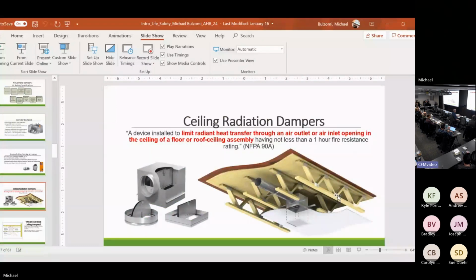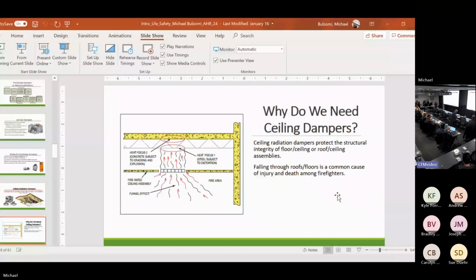Actuators, ceiling radiation damper. One job for a radiation damper: limit radiant heat transfer in a floor ceiling or roof ceiling assembly. So let's call this a membrane penetration. Right above us, I got a T-bar ceiling. Let's pretend the ceiling is fire rated. I got displacement diffusers everywhere, no ceiling, no overhead. But let's say I had a plaque diffuser right there. Well, everything is fire rated, but there's an opening for the neck of that plaque diffuser.